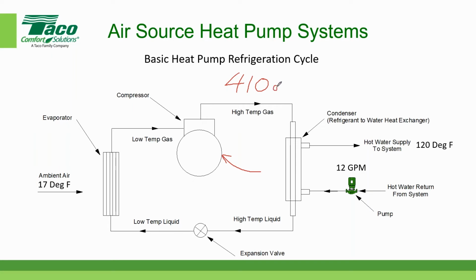Can I make a little A here? Yep. 410A. So let's follow the refrigerant as it flows through the piping system, and we'll start at the discharge side of the compressor. So it's connected to the compressor, and this little diagram shows the discharge. And this is the point at which the gas is compressed by the compressor. And so power goes into the compressor. And generally, we measure that power in terms of kW. And we're going to get into this a little bit later in our discussion. So that's the power input. And that's the amount of power it takes to rotate the compressor and to compress the gas.